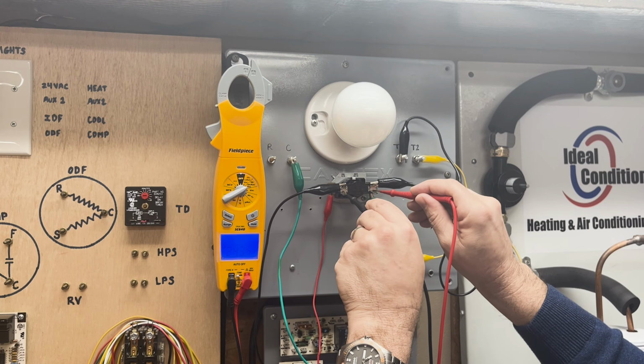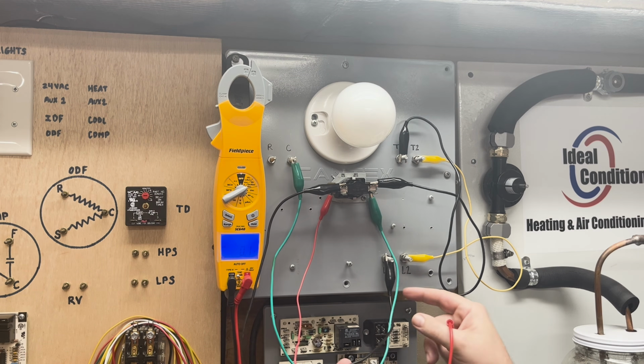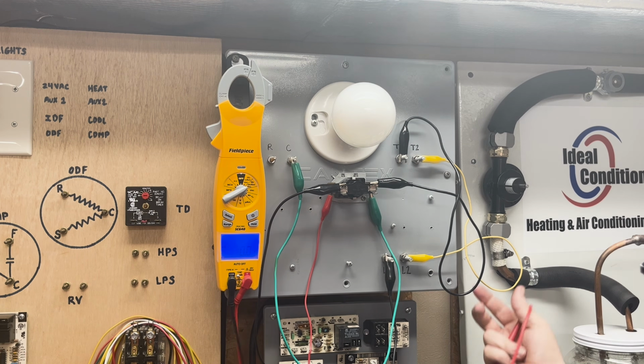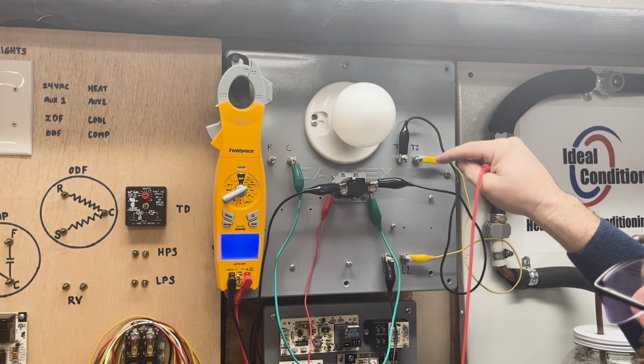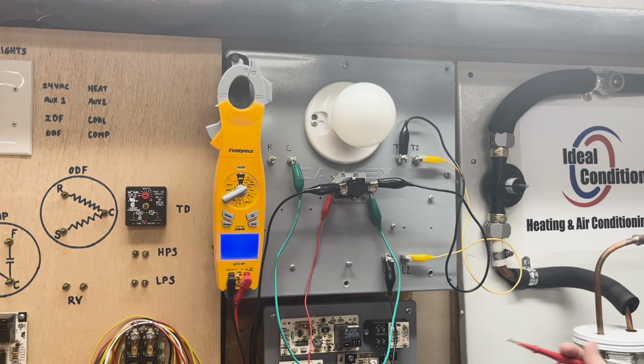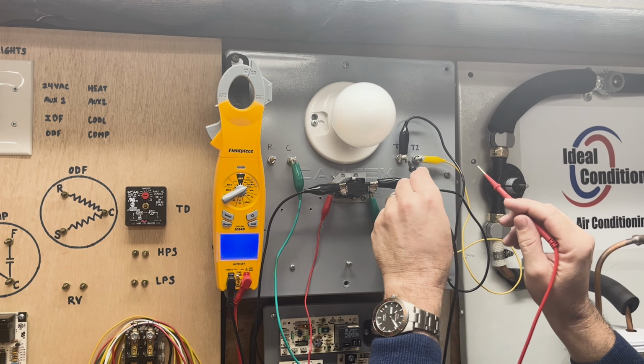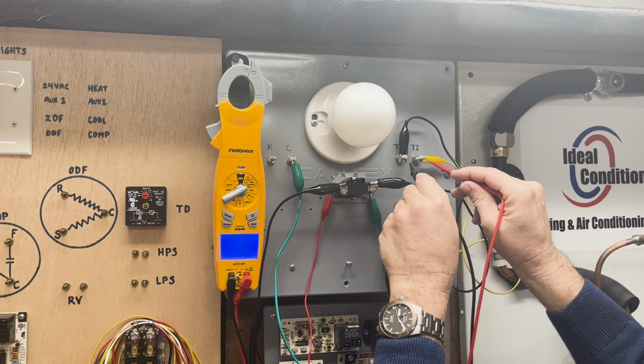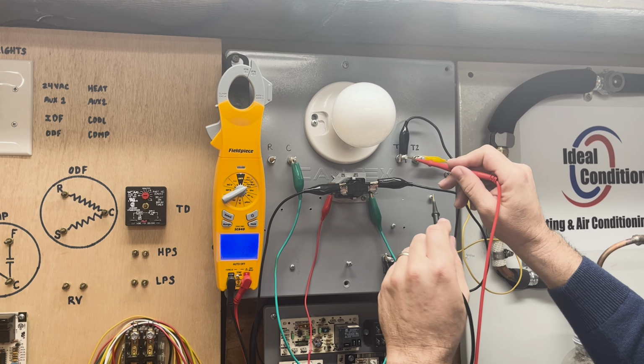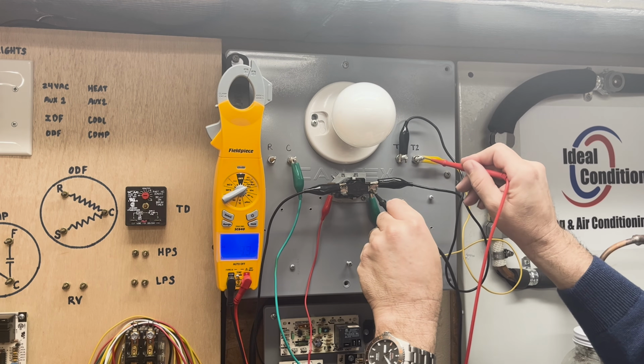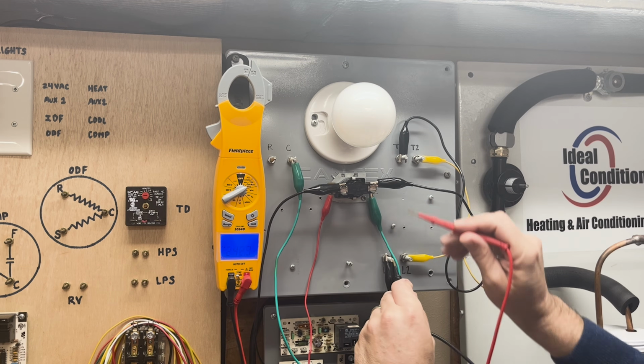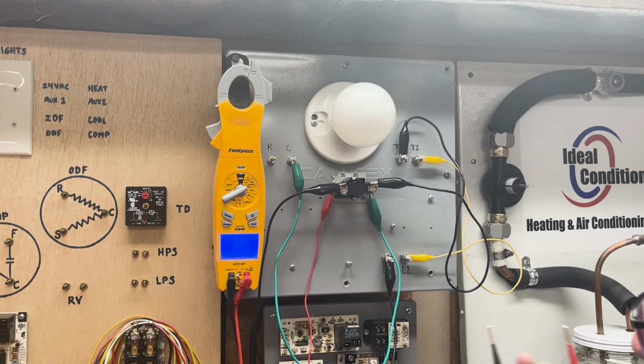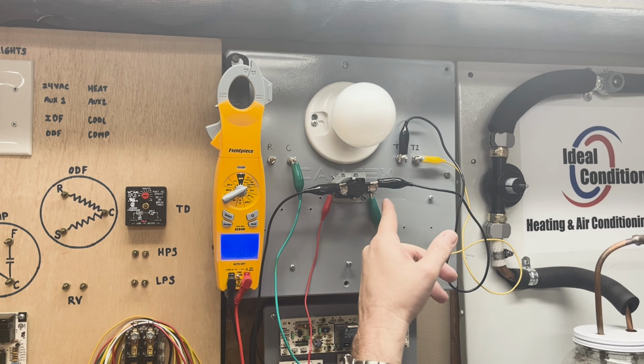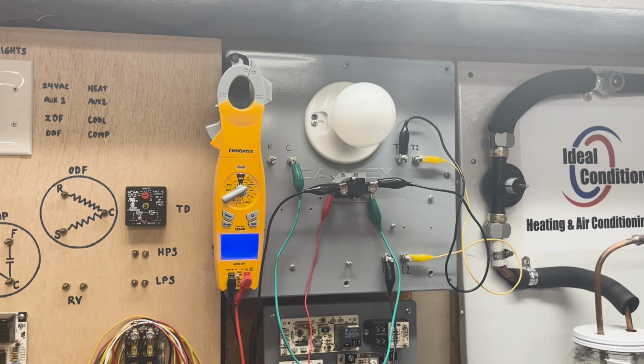Now we read 242 volts. If we look here, we have the black wire, which is L1 up to this point, right? But if we look over here, the yellow wire, we have L2 over to here. Well, through the load, I'm getting L2. So if I wanted to see voltage, for example, between L1 and L2, I have 242. Between T1 and T2, I have 0. Right? And if I wanted to see what my voltage is between T1 and here, it's going to be 0. 0. 0. 240. 240. That just really confirms that my relay is open, and there's nothing wrong with my load. Because if my load had a bad winding and the winding was open, then I would not be getting L2 here. So I have L1 plus L2 at this present time.